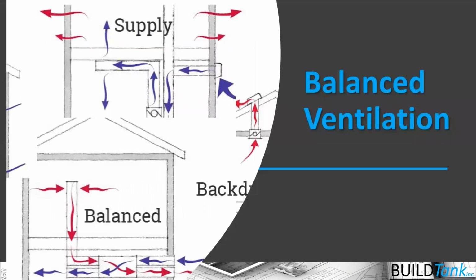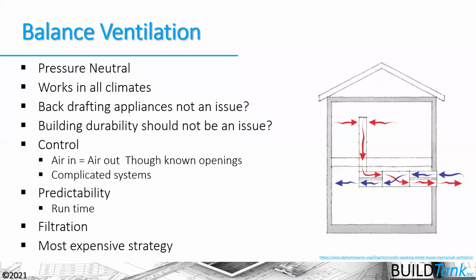So the next strategy that we want to talk about is the balanced ventilation strategy. Balanced ventilation is balanced because it's a neutral pressure strategy. We're taking air out and bringing in air at the same rate and at the same time, the same runtime period, so that we should have neutral pressure caused by the ventilation strategy that's being used. It can work in all climates, which is great.